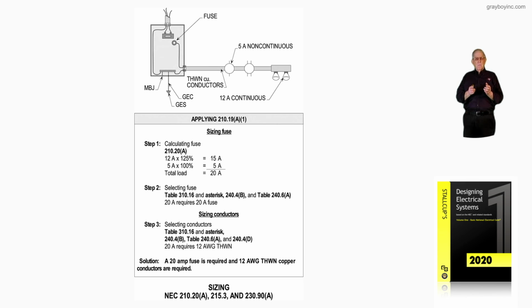So you see the 80% rule has been done away with in the NEC, and we just plainly say now 125% for continuous, for 3 hours or more operation. If less than 3 hours, it's 100%, and then we can have demand factors applied times 100%, and we would come up with the appropriate size protective device using a fuse or circuit breaker, and that's what Figure 9-39 is illustrating.